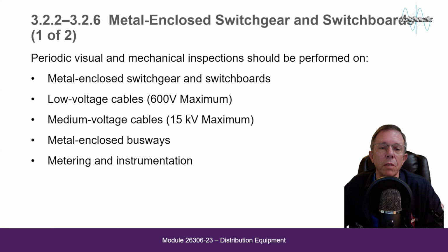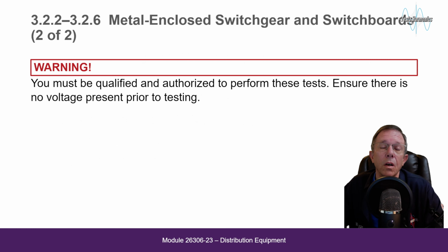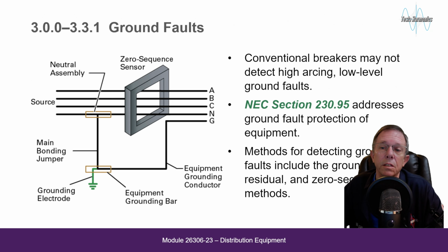Periodic visual and mechanical inspection should be performed on metal enclosed switchgear and switchboards, low voltage cables, medium voltage cables, metal enclosed busways, and metering and instrumentation. Warning: you must be qualified and authorized to perform these tests. Ensure there is no voltage present prior to testing.